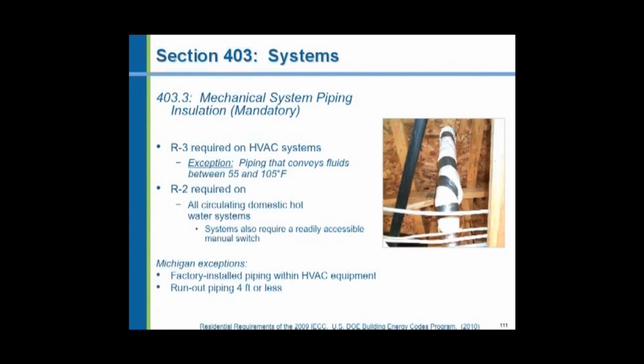Now we come to piping, referring to hydronic heating piping. Piping carrying fluids above 105 degrees, which would be hot water heating. Typically we would see temperatures of 160 to 180 in the wintertime. Or chilled water and refrigeration piping below 55 degrees must be insulated to a minimum of R3. And as we know, fiberglass insulation has an R value of 3 per inch. So this is equivalent to 1 inch of fiberglass or the equivalent foam plastic insulation.